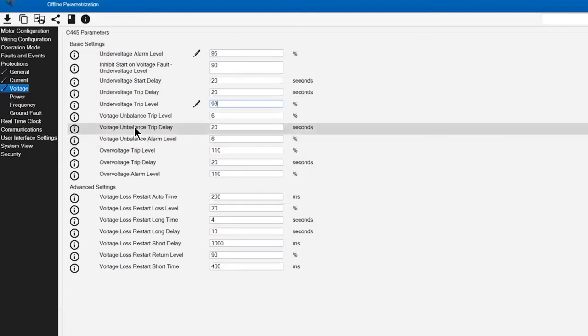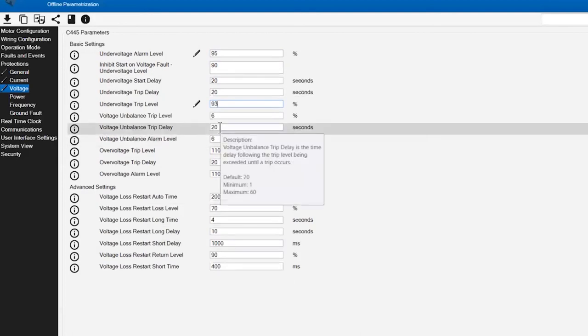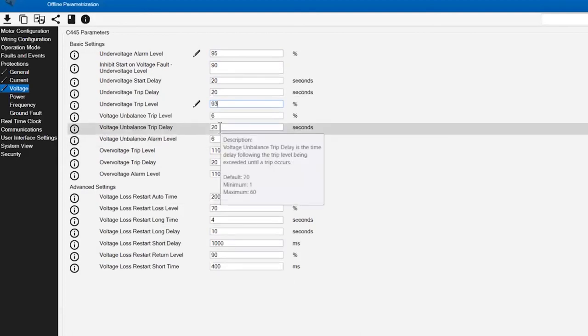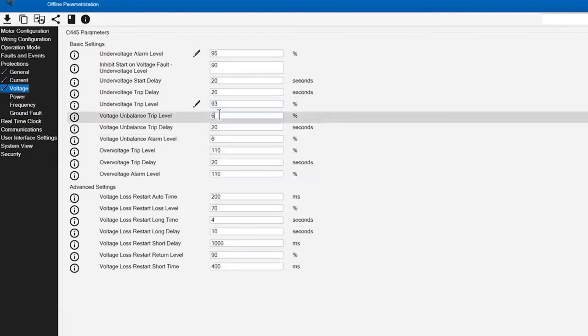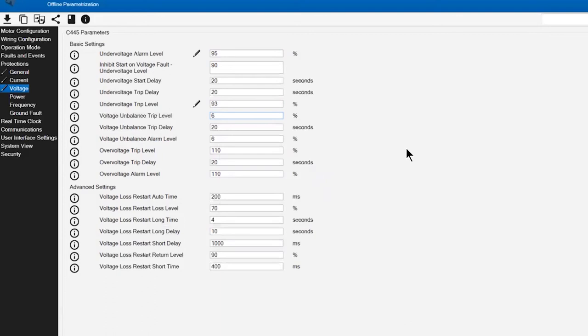The other predominant function that I would typically set is once again the imbalance. There is an association between voltage imbalance and current imbalance in a motor. It's generally for every 1% of voltage imbalance you have will equate into 6 to 8 times the current imbalance. So remember where we really lowered that current imbalance setting to be more in line with NEMA design of motors.